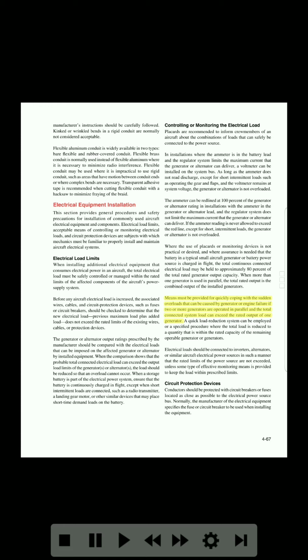If two or more generators are operated in parallel, and the total connected system load can exceed the rated output of one generator, a quick load reduction system can be employed, or a specified procedure, where the total load is reduced to a quantity that is within the rated capacity of the remaining operable generator or generators. Electrical loads should be connected to inverters, alternators, or similar aircraft electrical power sources in such a manner that the rated limits of the power source are not exceeded, unless some type of effective monitoring means is provided to keep the load within prescribed limits.